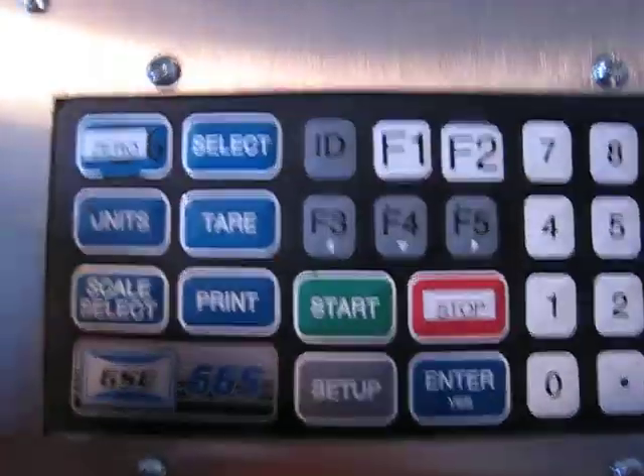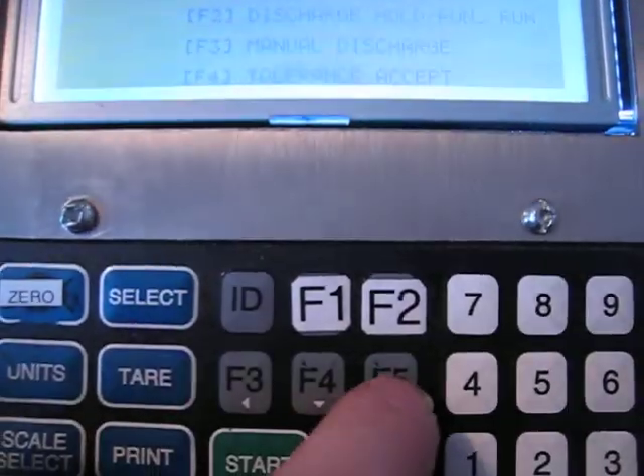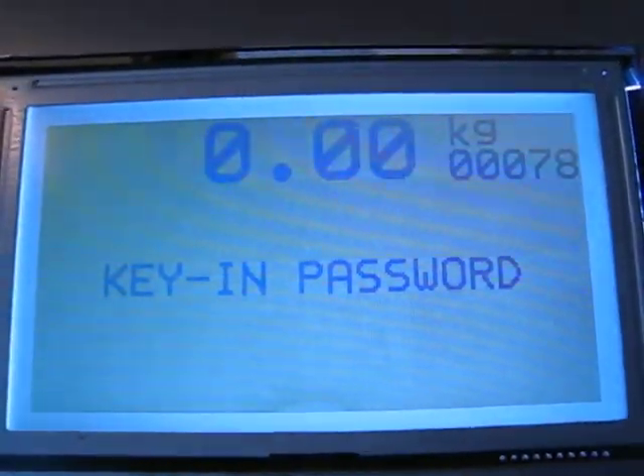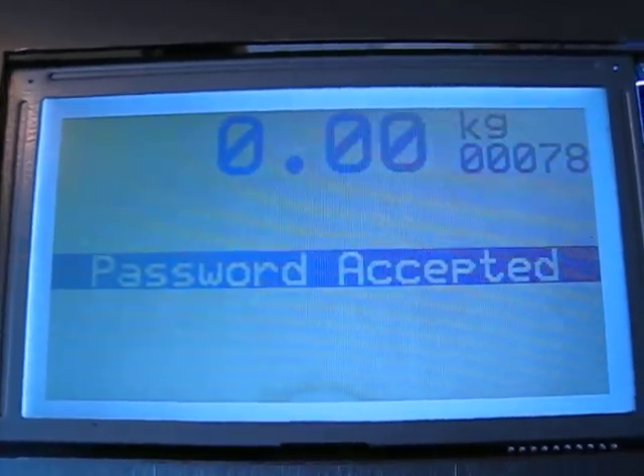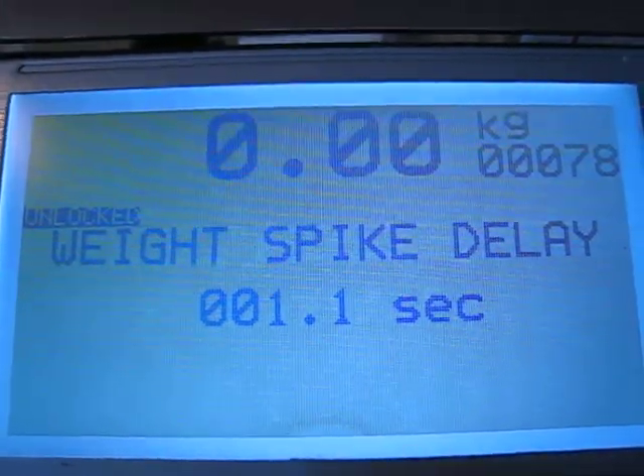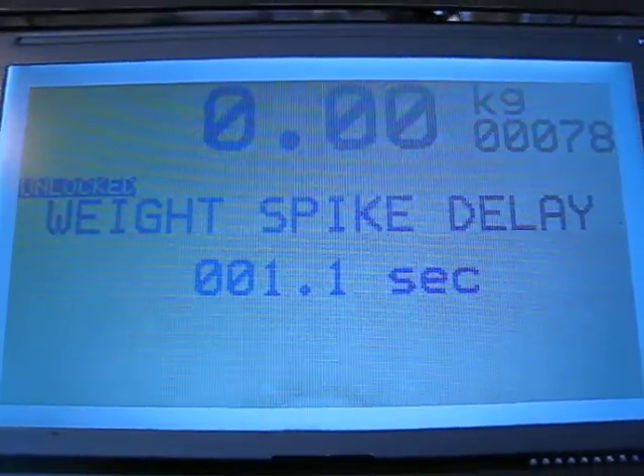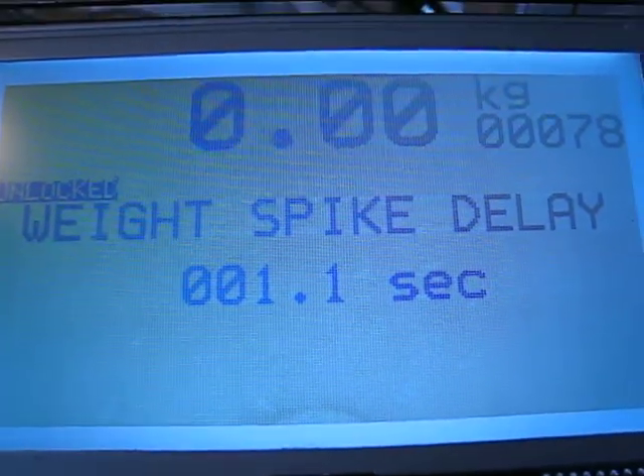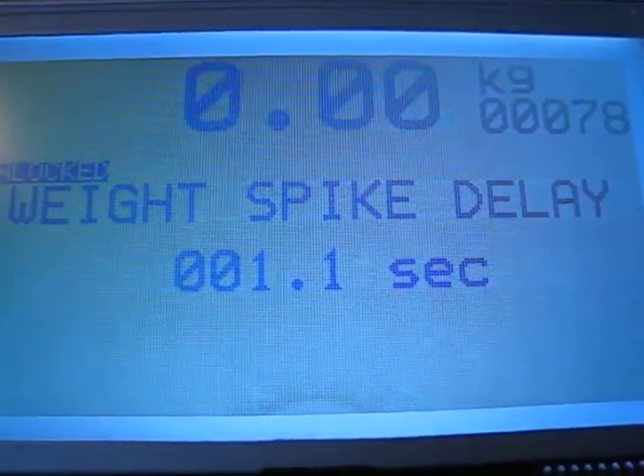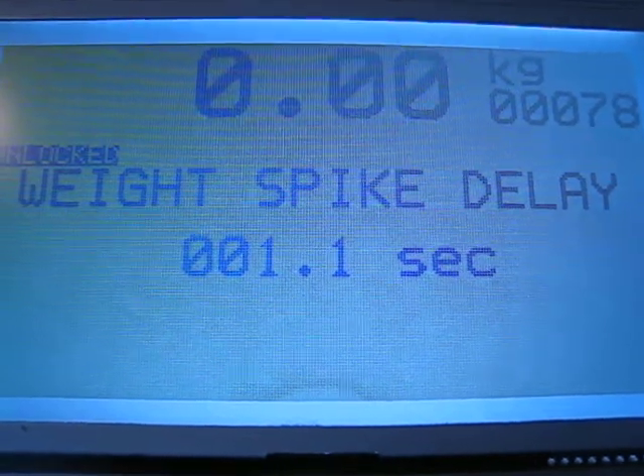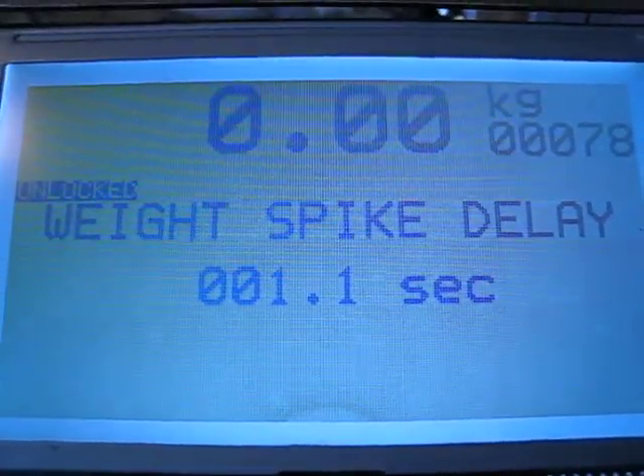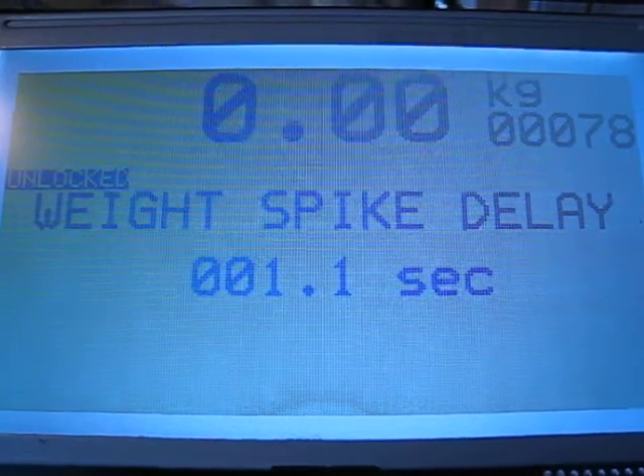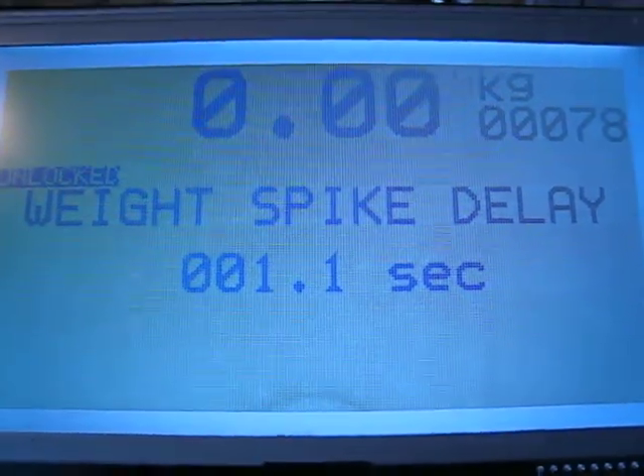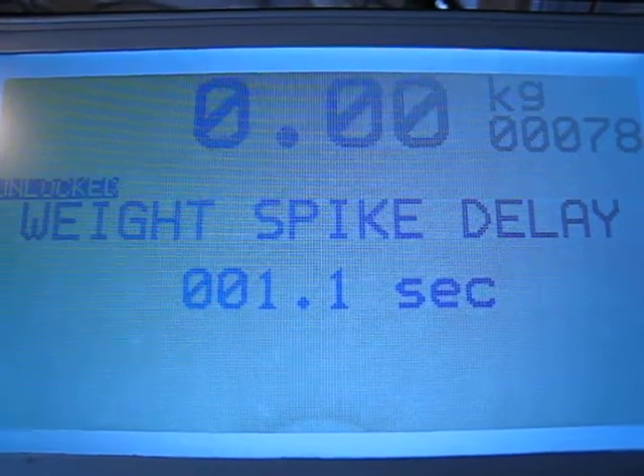Now there were adjustable filters in the program, so from the main screen, if we press the F5, it asks for a password. We enter our password, and now if we press the F1 to arrow up, we see it has a bounce timer. So this is when the scale starts filling, it ignores set point 1 for this duration of time. Now there should really ideally be two separate bounce timers. The fast bounce timer should be 0.7, and then there should be a second one that's a slow bounce timer, which should be 1 second.